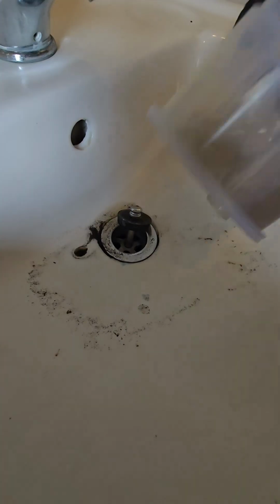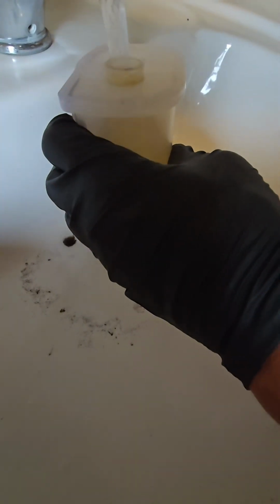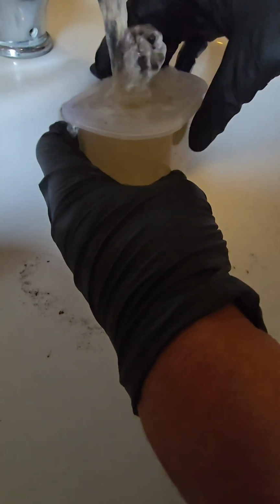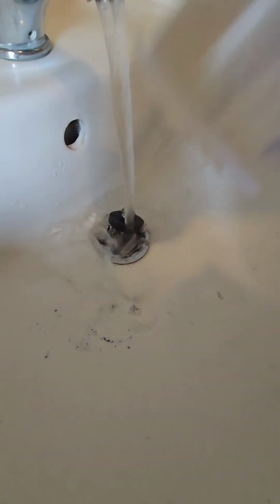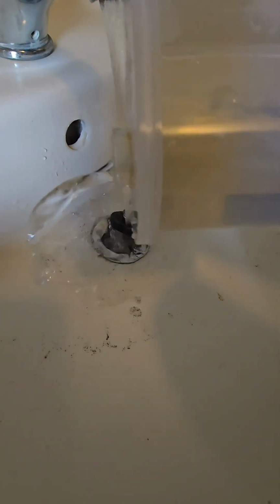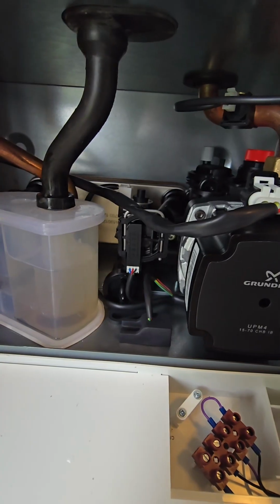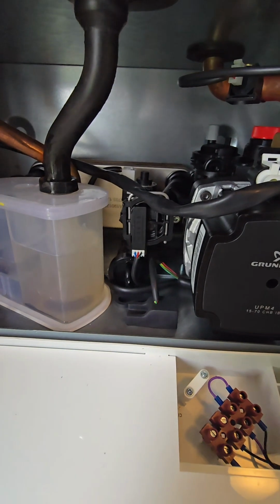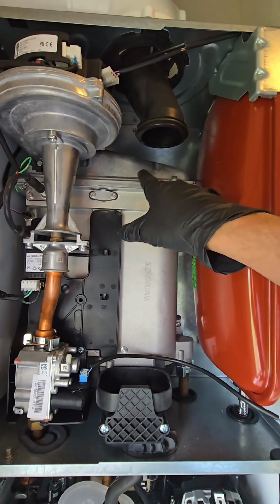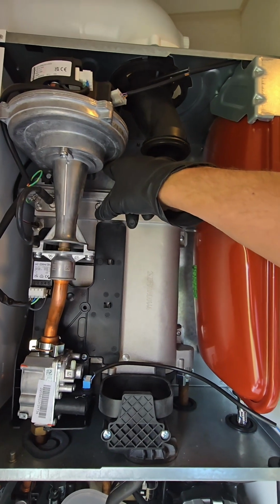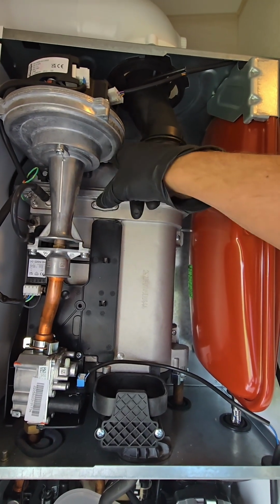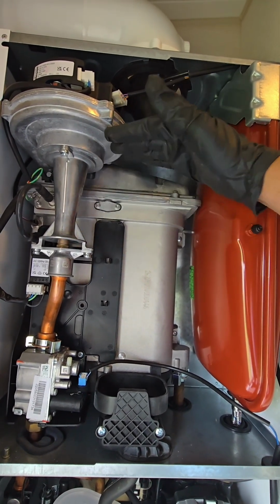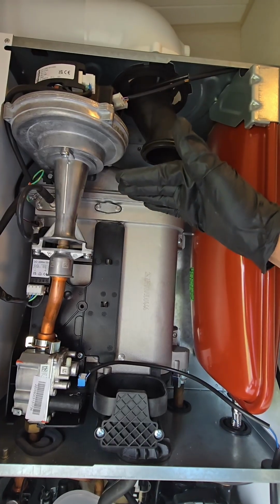Any deposits, and rinse it through. Now keep doing this until the trap is fully clean. Trap refitted in reverse order. So that's the burner reinstated, tightening all 4 bolts opposite diagonally to ensure that it is fully pulled down and evenly sealed.